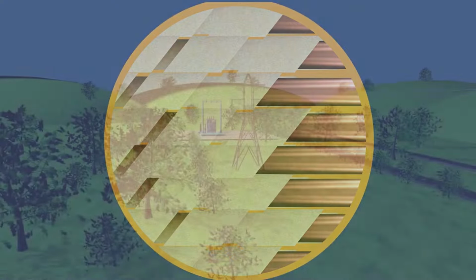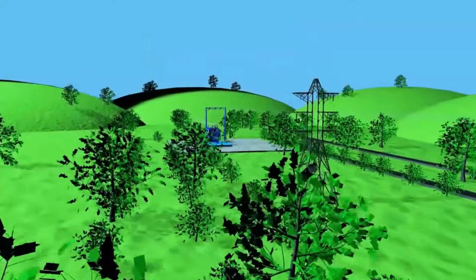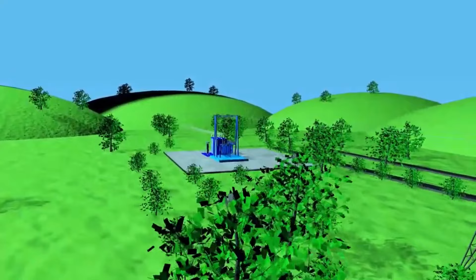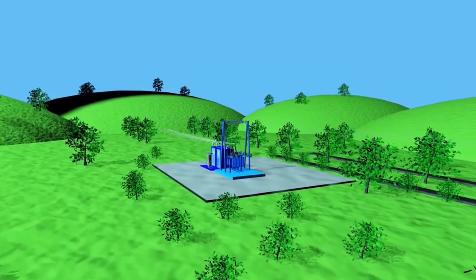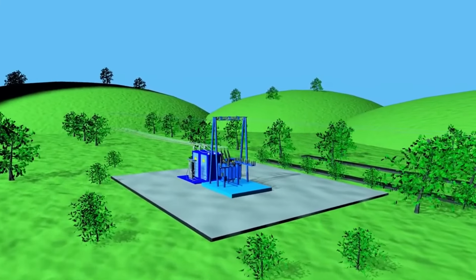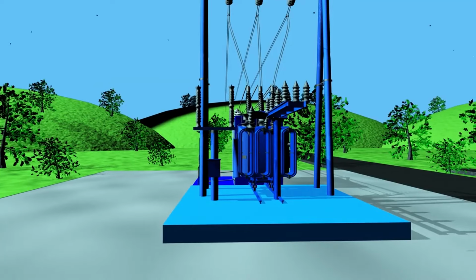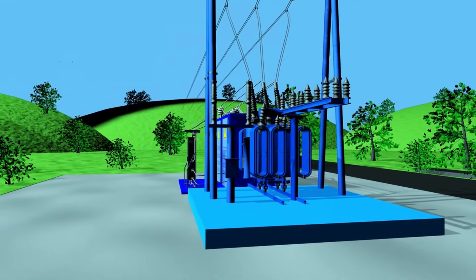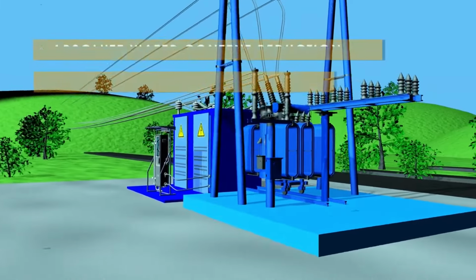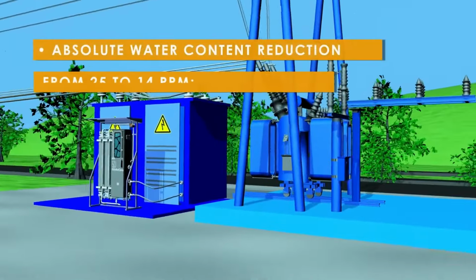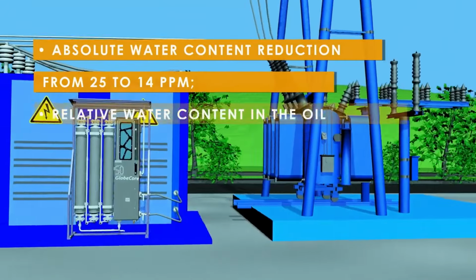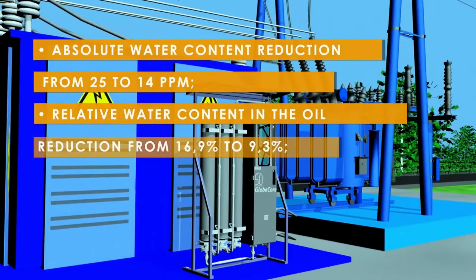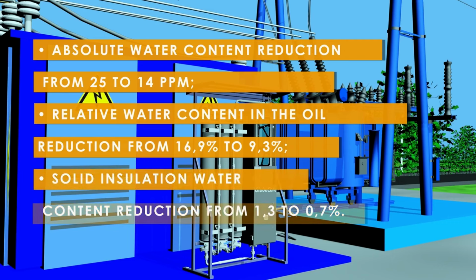Now, a practical example. One of GlobeCore clients in Latin America used a CMM-260C unit to dry an energized transformer continuously for 8 months. The following results were achieved in that time. Absolute water content reduction from 25 to 14 parts per million. Relative water content in the oil reduction from 16.9% to 9.3%. Solid insulation water content reduction from 1.3 to 0.7%.